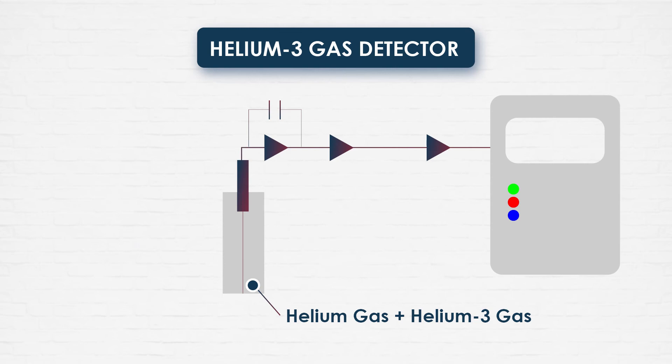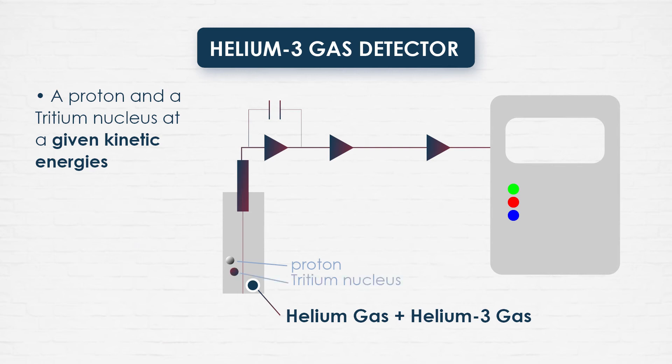By means of electrodes, a proper electric field is set within the chamber. So, when a thermal neutron enters the chamber, it is likely to react with the helium-3 nucleus of the gas. The reaction produces a proton and a tritium nucleus at a given kinetic energy.